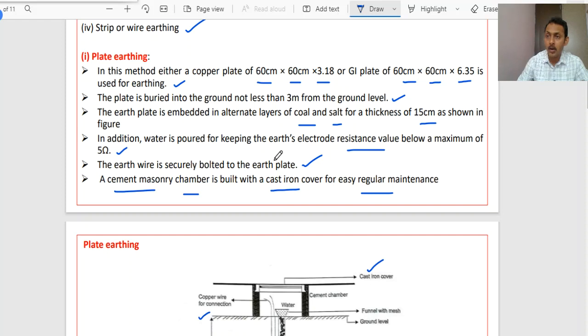We have already discussed one protective device, the earth leakage circuit breaker, which protects persons or operators from electric shock by detecting earth leakage currents. Depending upon the potential difference established between the person and the equipment surface, some amount of current will flow. It also depends upon the resistance of the human body, which varies with whether the skin is dry or wet while touching the electrical equipment. Based on that, the resistance offered by the human body will change, right.